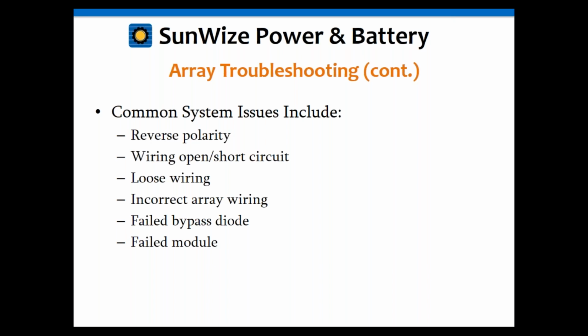Incorrect array wiring: if you've got multiple solar modules being wired in series and parallel, it's easy for somebody to get the wiring confused. I've seen that happen before. Let's say you might have 4 solar modules and you may have gotten 2 wired correctly, the other 2 aren't. What can happen sometimes is that you can run great for the summer when you have extra solar, and then come in the fall when you really need this whole solar array, all of a sudden having half the array not wired correctly starts to fail. So this might be one of those where, hey, it ran great all summer long. We installed it in the spring and it ran great, and then in the fall you had a problem. That's usually when I tell people to double check their array wiring, because that's a common one there.